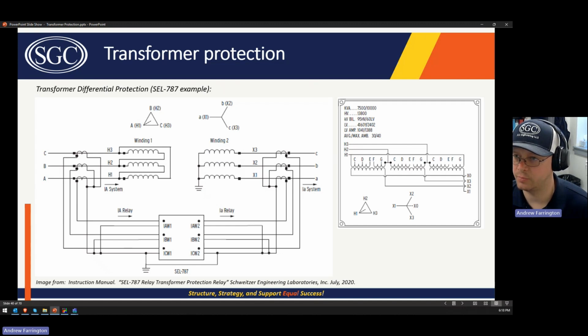Last year, I used what I think is an interesting example from CMP. Their 345 kV system has a phasing of ABC, and their 115 kV system has a phasing of 1, 2, 3. And A is not related to phase 1. A is actually phase 2, and C is phase 1, excuse me. So for their 345 to 115 kV autotransformers, they actually wire A to current input A, B to current input B, and C to current input C. And then they wire 1 to the A current input, B to 2, and then C to 3, or 3 to C.